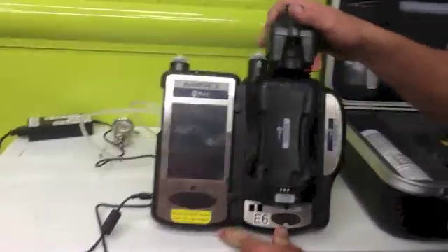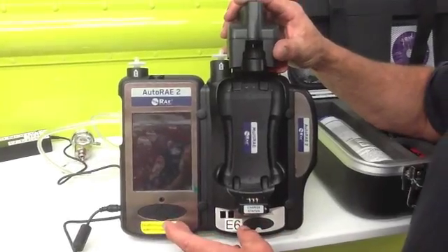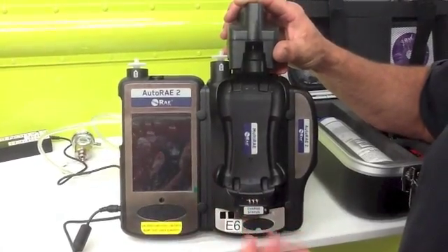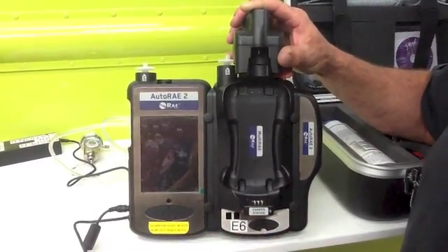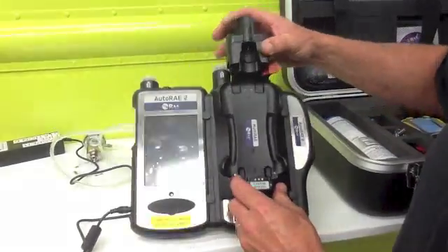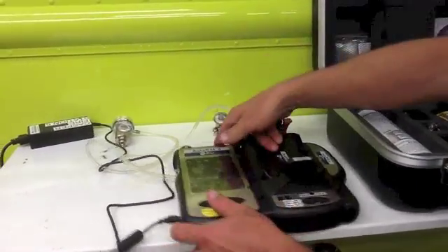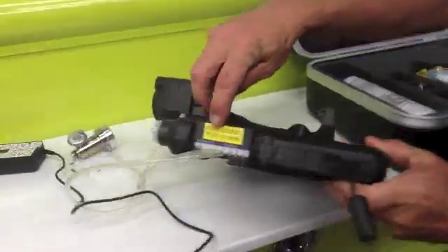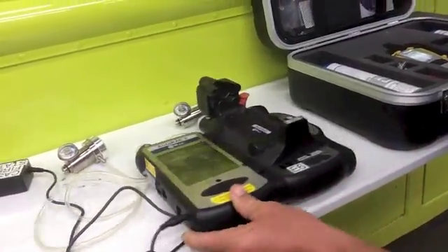This is your new AutoRAE 2 — it's a computer base station with a charging unit, and it will walk you through how to bump test and how to calibrate. Bump tests are once a month; calibration is every 180 days. You have two regulators which obviously go on your bottles, and then they go into the ports on the side — Port 1 and 2. It's labeled and easy for you to figure out.